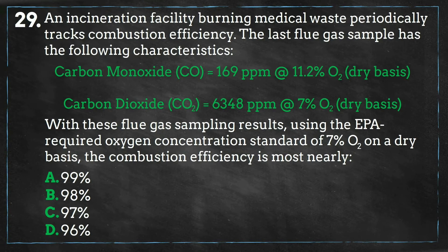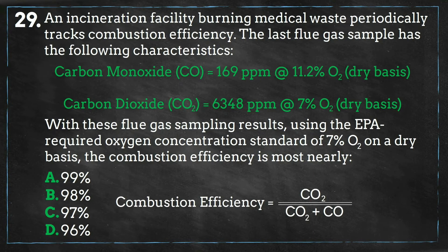This problem shows that we have some measurements of carbon dioxide and carbon monoxide, albeit the carbon monoxide concentration is much smaller. This shows that we do not have complete combustion coming out of the exhaust stack. So to find the combustion efficiency, we will take the concentration of carbon dioxide divided by the sum of the carbon dioxide and carbon monoxide concentrations.